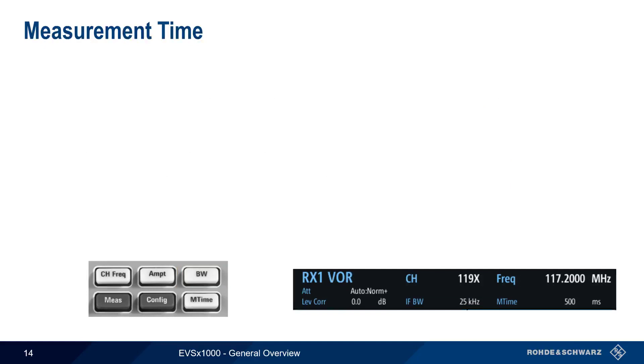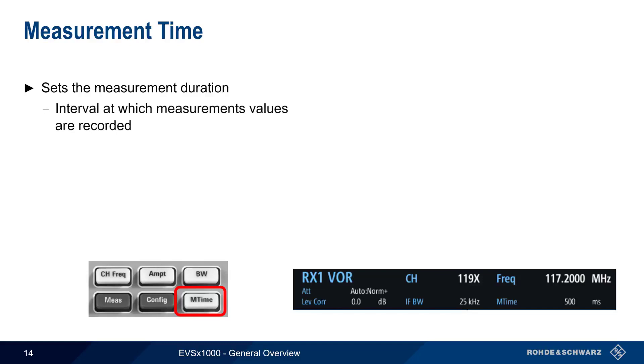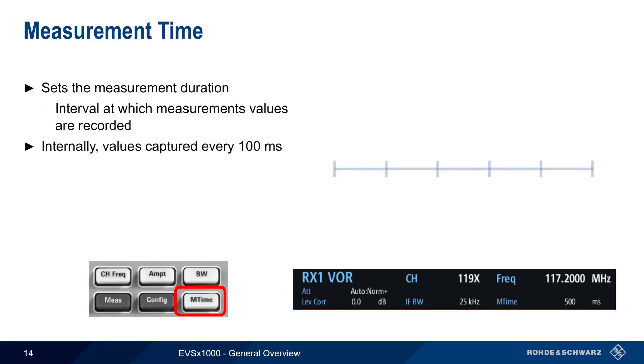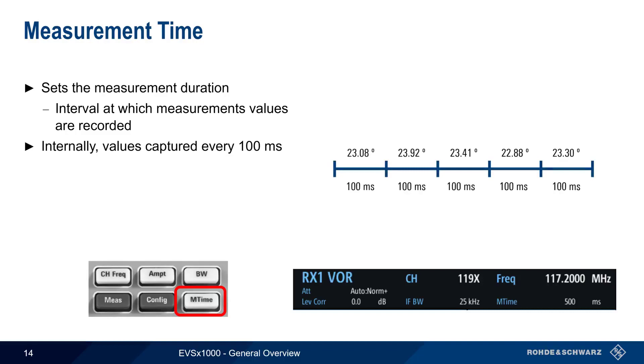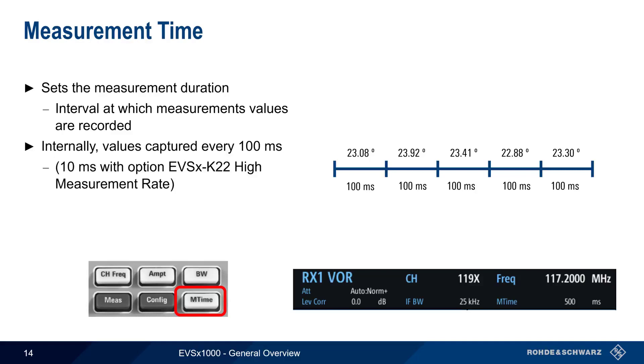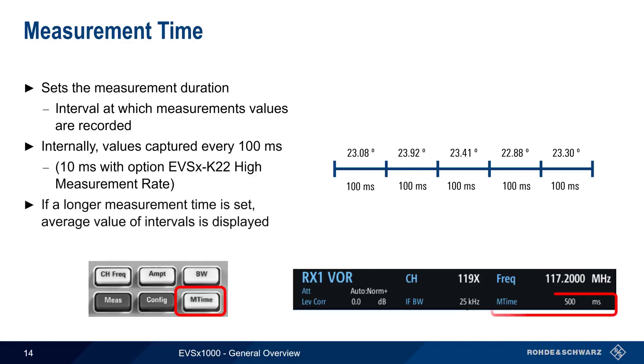The last general parameter is measurement time, which sets the measurement duration — specifically, the interval at which measurement values are recorded. Internally, this interval is 100 ms, although it can be reduced to 10 ms with the K22 high measurement rate option. It's possible to configure a longer measurement time, in which case the average is reported. For example, a 500 ms measurement time means that five 100 ms measurement intervals are averaged and reported.